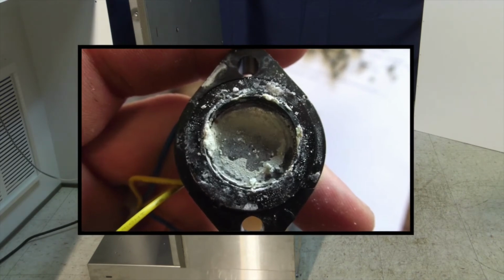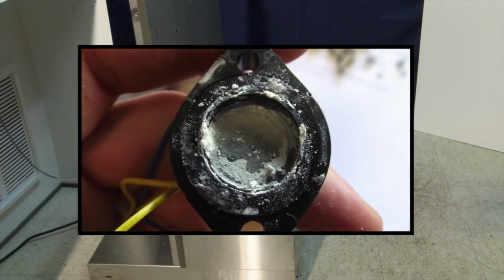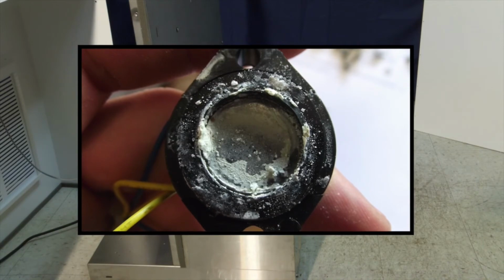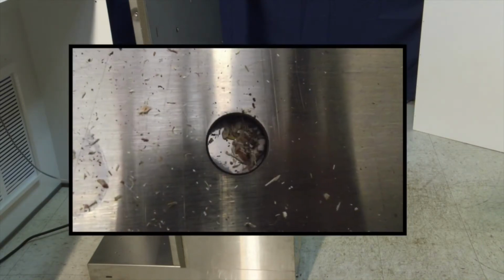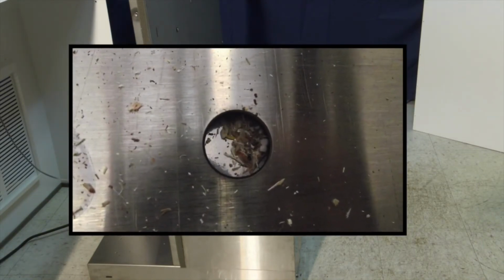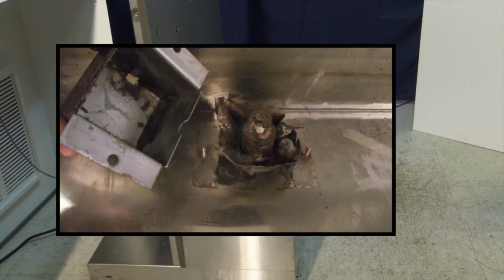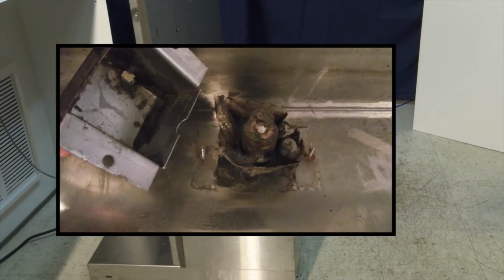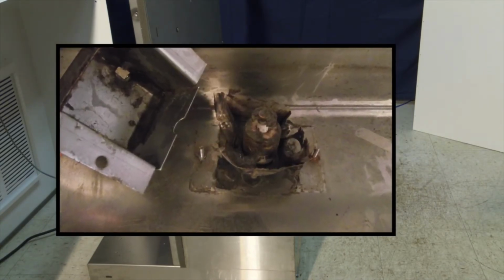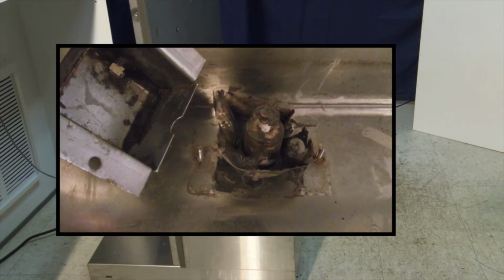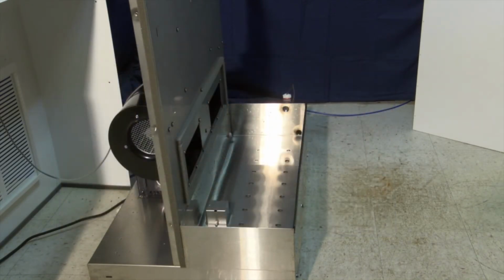If the water pan is allowed to build up with mineral scale, organic growth, or other contaminants from your environment, this can stress your transducers and severely shorten their lifespan. If the float is not clean and clear, this will inhibit it from moving up and down freely and will keep your mist-free unit from working properly and can even damage it.